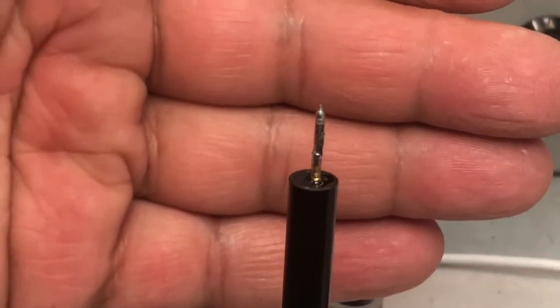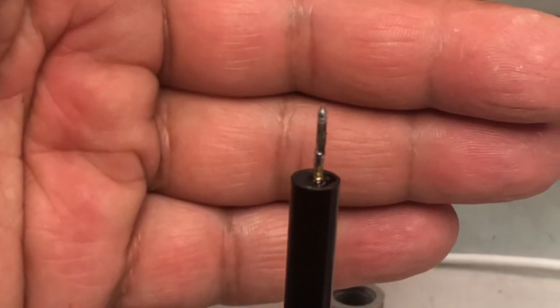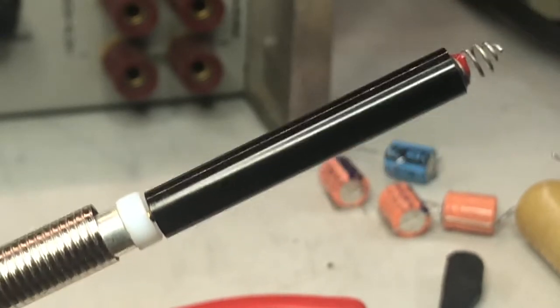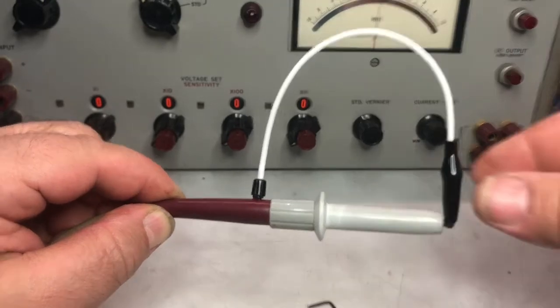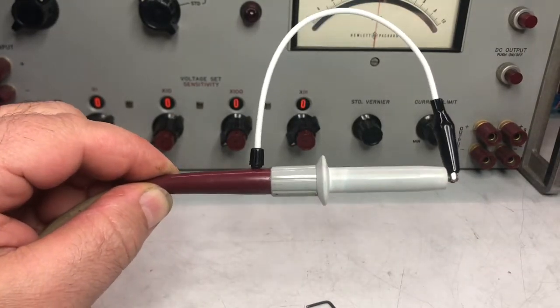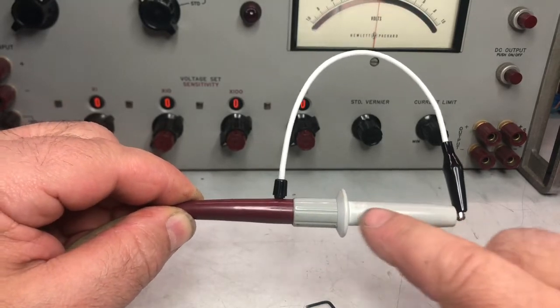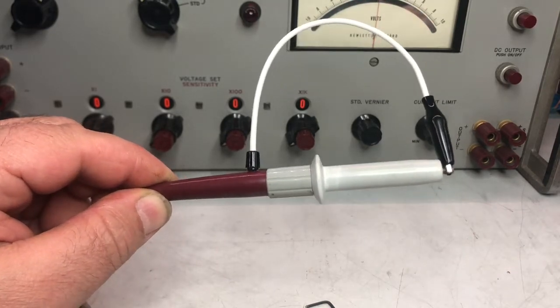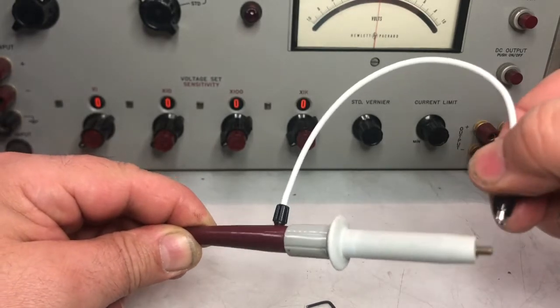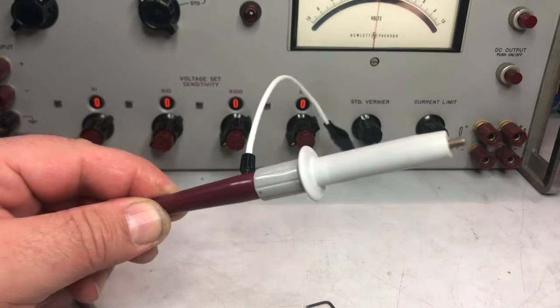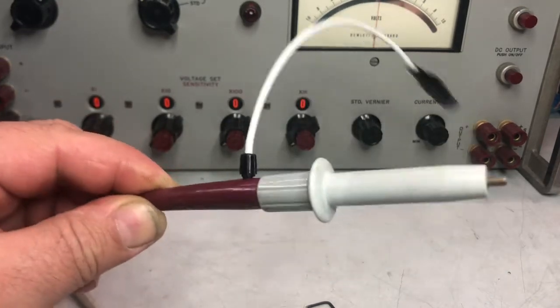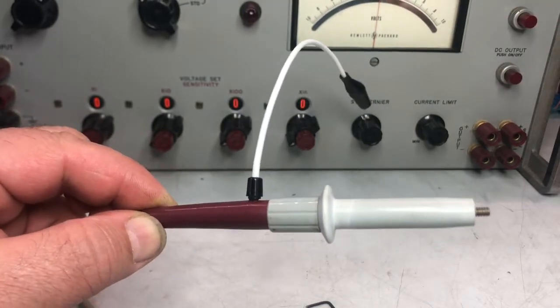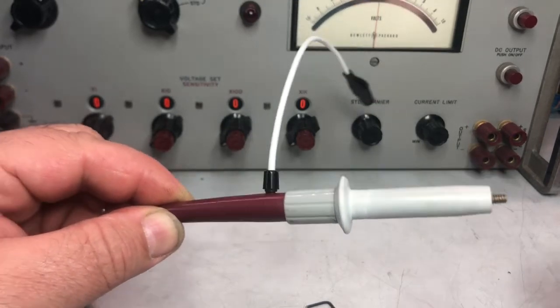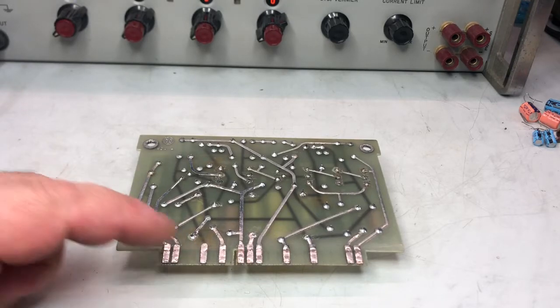So I need to keep this something here to make up focus. So I can now reassemble the probe and check the continuity. And by the way, now it fits in very precisely and tight, so really happy for the result. This is the result. So the probe is reassembled. I need to restore a bit this insulation part, and I have to machine a new probe tip, since I only have this screw at the end. But all in all, it seems to be fine, and the continuity is pretty fine. So I think I can consider it repaired. Well, I have cleaned this board.